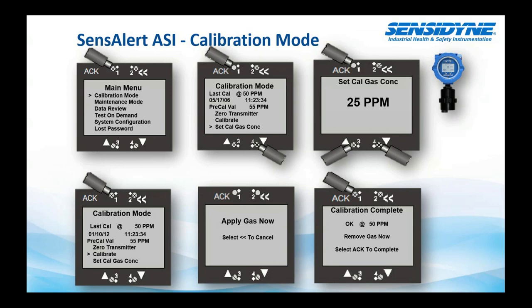So then we would go and set our gas concentration. In this case, we're calibrating a 50 ppm sensor. We want to calibrate to 50% of the range, which would be a 25 ppm gas concentration. And then the next part of that menu is where it says calibrate. You acknowledge that, and it tells you apply gas now. Once you apply the gas and it's in this mode, it's now in the calibration mode. It goes through the calibration process itself.